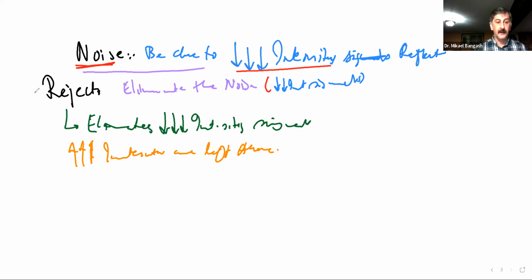So reject is a function where you say we need to get rid of this noise here. So they establish a mechanism which is only going to remove the low intensity signals of the image, which constitute what's going to be noise, but it's not going to do anything to the strong intensity signals that actually produced our actual image. Did that make sense? Right. So because it is selective in that way, its selection of elimination goes towards the low intensity signals.